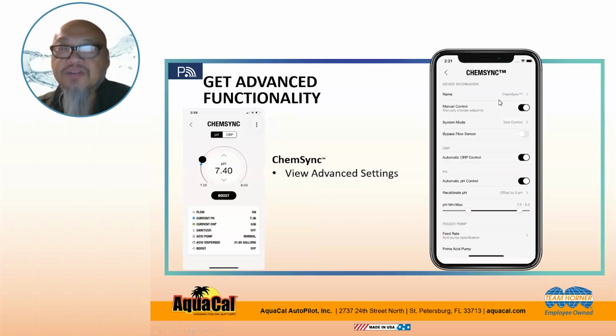Again, you can name your ChemSync unit. System is in total control mode, so it's doing the ORP and pH operation. You can see we've got different toggle switches, manual control if you want to override and choose your own set points instead of using the factory set points. Automatic ORP control, automatic pH control, those are both set on for right now. Calibrate pH: if at some point you have a different pH on your test than what's reading, we can match the reading on the unit to your water chemistry test.